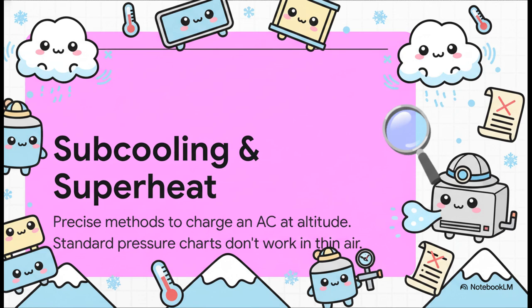They can't just pull out a standard pressure chart, it's basically useless up there. Instead, they rely on advanced methods called subcooling and superheat, taking hyper-precise temperature readings of the refrigerant itself to get the system charged just right for the lower atmospheric pressure.